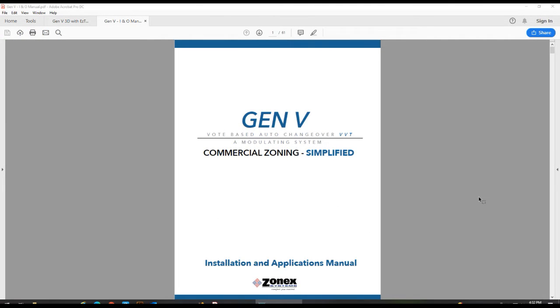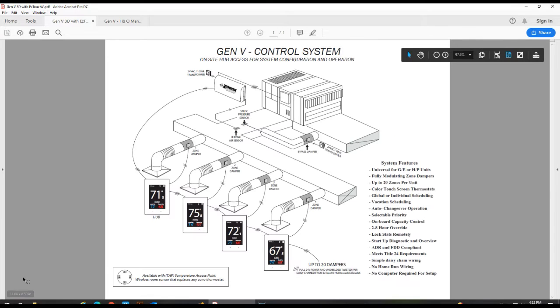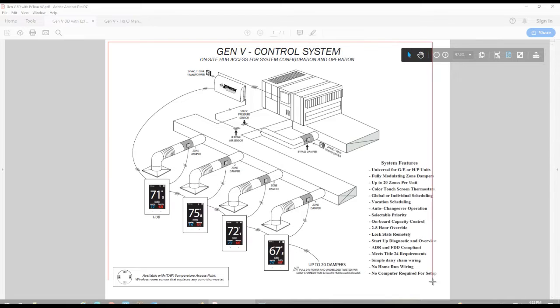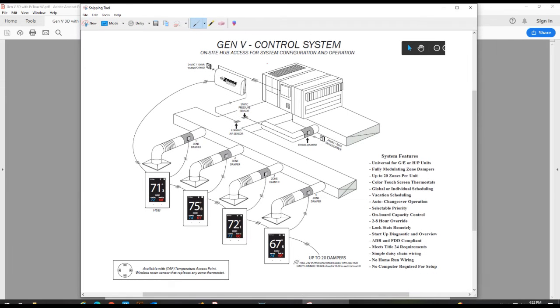Today we'll be covering the Gen V vote-based auto changeover VVT zone control system. It controls up to 20 zones and utilizes a hub thermostat to send commands and configure our Gen V controller and zone thermostats. We're going to go ahead and start off with the wiring aspects of the control system and how it's connected with this 3D overview to each zone and damper it controls.